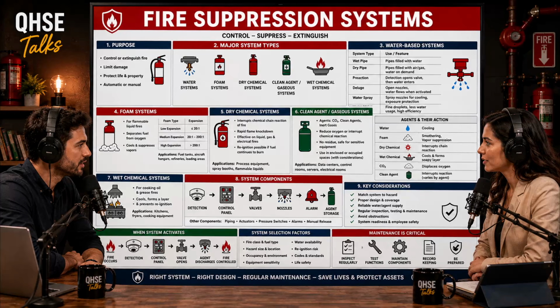Okay, I am going to push back on this design logic a bit. Sure. If the wet pipe system is instantaneous, why are we accepting the massive delay of a dry pipe system? The air has to bleed out, the valve has to trip, the water has to travel through hundreds of feet of empty pipe. NFPA says water has to reach the furthest head within 60 seconds. But in a fast-moving fire, 60 seconds is an eternity. Isn't speed the most critical factor?